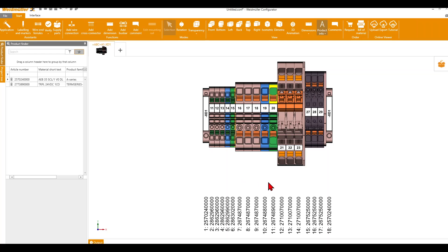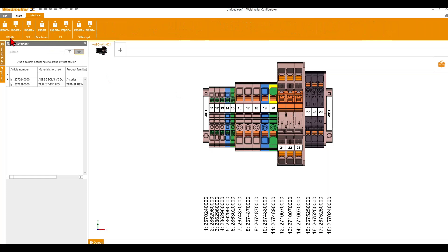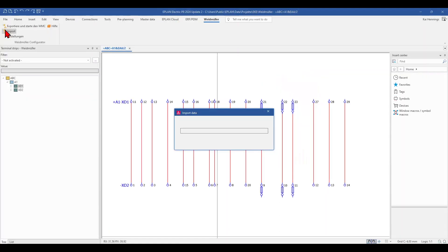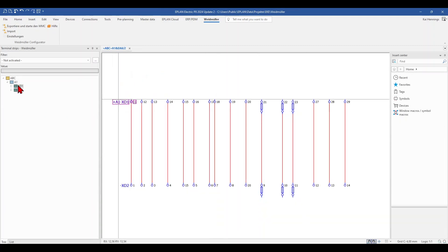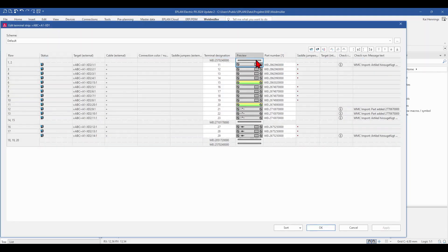Now we have changed our terminal strip a little bit and added the accessories, and we want to exchange the data with ePlan so that we also have these parts in ePlan. Therefore we go to Interface and you can see ePlan Export. Now the Weidmüller Configurator sends the data to ePlan and makes the auto-correction for the terminal strip. You can now see that I got the end brackets and the end plates, all in the right sequence and position — exactly what I had done in the Weidmüller Configurator.